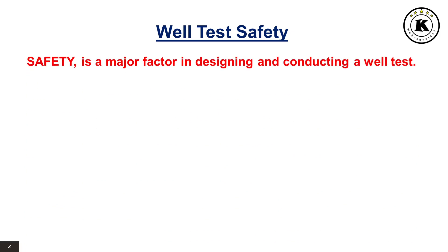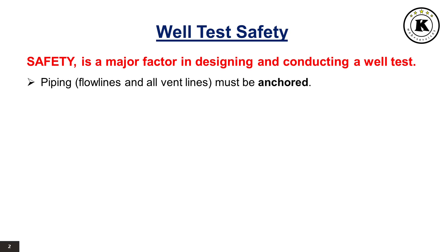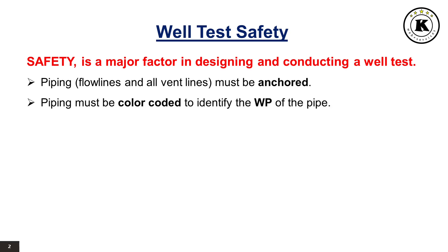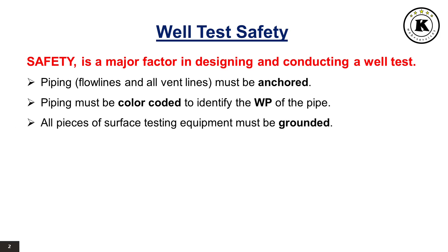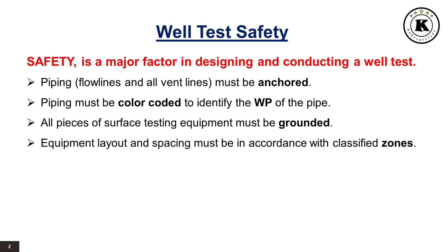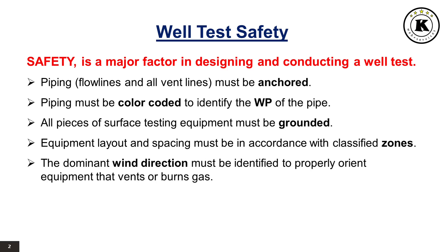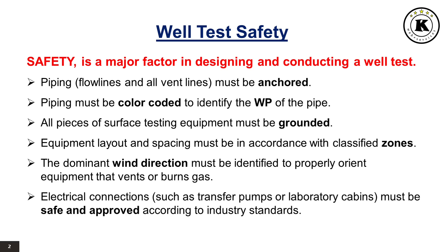Safety is a major factor in designing and conducting a well test. Piping, flow lines, and all vent lines must be anchored. Piping must be color-coded to identify the working pressure of the pipe. All pieces of surface testing equipment must be grounded. Equipment layout and spacing must be in accordance with classified zones. The dominant wind direction must be identified to properly orient equipment that vents or burns gas. Electrical connections such as transfer pumps or laboratory cabins must be safe and approved according to industry standards.